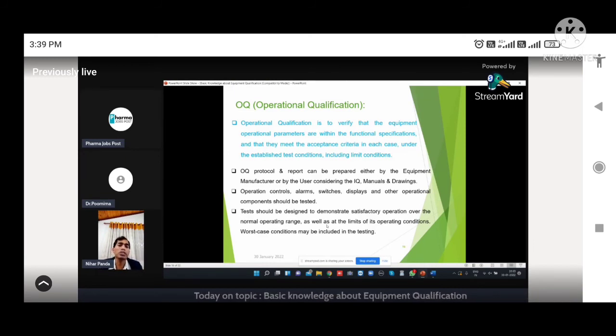OK, that means you have to check the functional part, whether it is operating as per our requirement, whether all the limits are available, whether it is slow speed, high speed, medium speed, all the things are available, whether those are working as per the requirement, whether any alarm system is there. All the things need to be verified during the OQ. OQ protocol and report can be prepared by the user department or by the manufacturer.